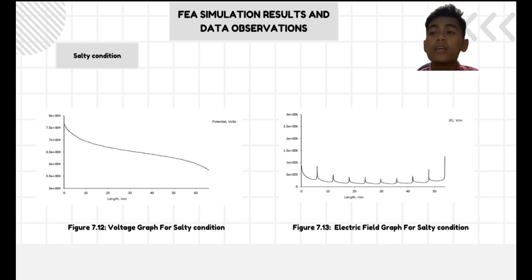We can see that in wet condition, the electric charge increases exponentially compared to salty condition, because in a salty condition, salt deposit on the surface of the insulator creates a conductive path, but its conductivity is typically lower compared to water. As a result, the electric field intensity along the surface of the insulator is generally lower in a salty condition compared to a wet condition.